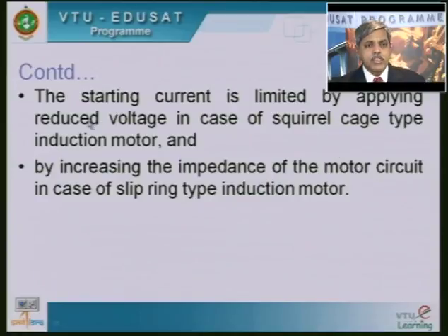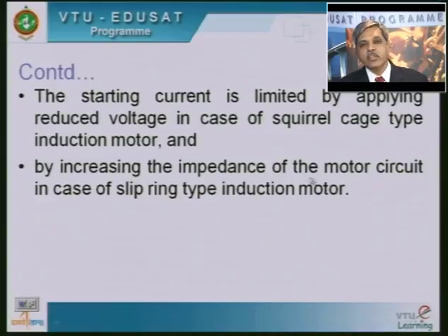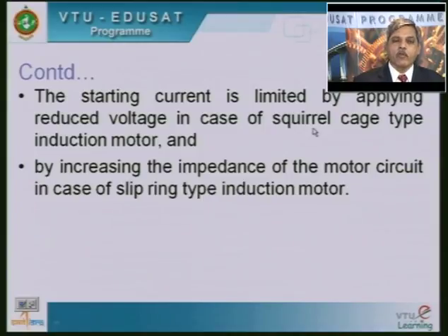So, the starting current is limited by applying a reduced voltage in the case of a squirrel cage type induction motor, and by increasing the impedance of the motor circuit in the case of a slip ring type induction motor. In yesterday's session, I told you about the classification of induction motors. In one of the rotor constructions, where the rotor is made up of squirrel cage type, it is not possible to add any resistance into the rotor circuit.